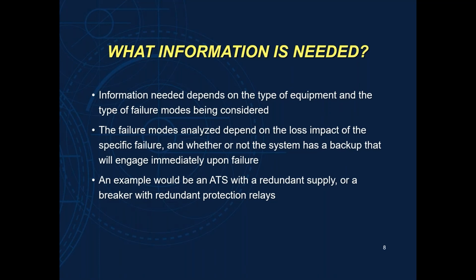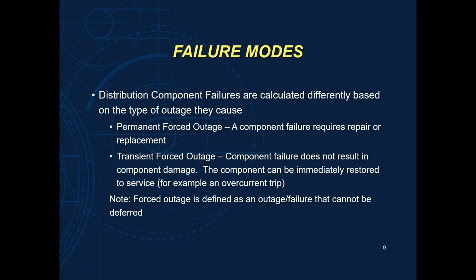Another thing would be if you have a circuit breaker trip and it's just an overload trip, and you're going to reset it real quick. Well, that's completely different than having a circuit breaker that blows up, for instance, where you have to pull it out of the system and replace it with a new one. So there's a lot of different pieces and parts to this calculation and to the philosophy behind the reliability determination. We could have permanent forced outages, things that require a repair or replacement. These are going to be a long-term type of outage. And then you have your transients, which are things like an overcurrent trip where they can be reset. Okay, so that's how we determine what types of failures we're going to be analyzing here.